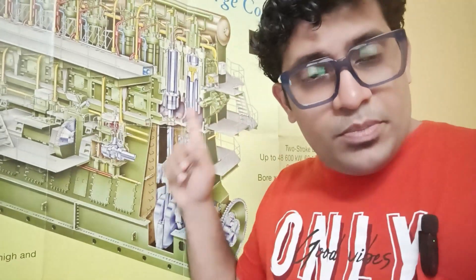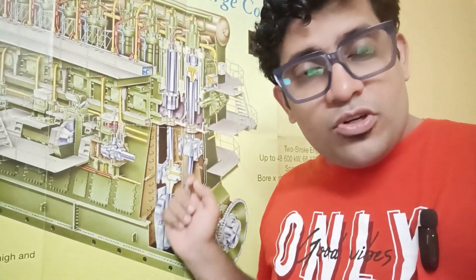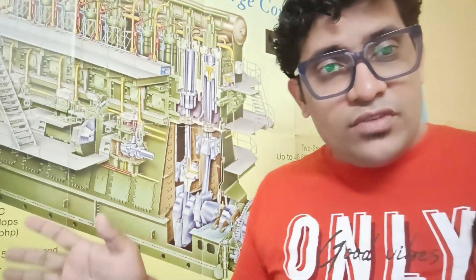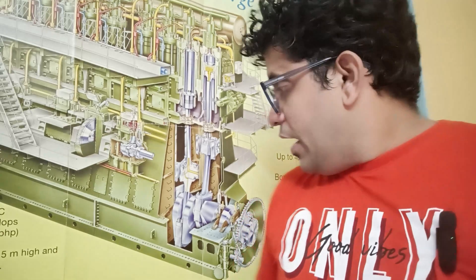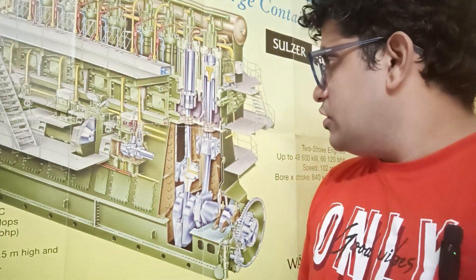Lube oil flows to the crosshead, from the crosshead it goes to the piston, from the piston it comes back to the crosshead, and from the crosshead it goes to the sides — the shoe guides and sliding surfaces. All the oil is then scraped down back to the crankcase.